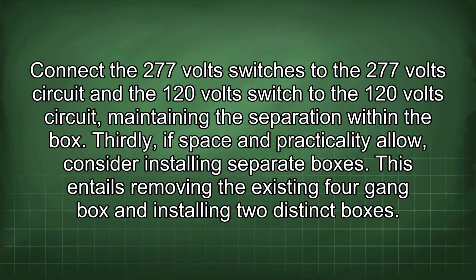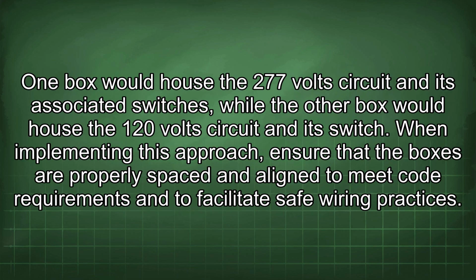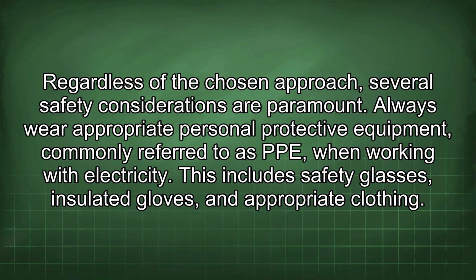Thirdly, if space and practicality allow, consider installing separate boxes. This entails removing the existing four gang box and installing two distinct boxes. One box would house the 277 volt circuit and its associated switches, while the other box would house the 120 volt circuit and its switch. When implementing this approach, ensure that the boxes are properly spaced and aligned to meet code requirements and to facilitate safe wiring practices. Regardless of the chosen approach, several safety considerations are paramount.